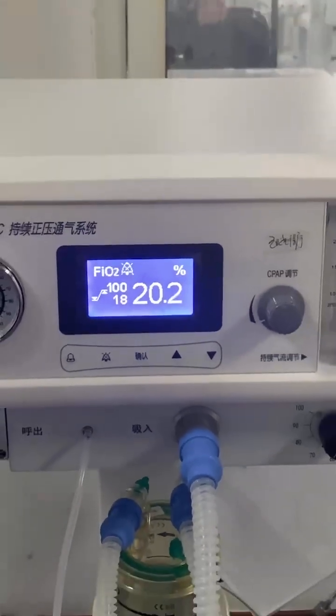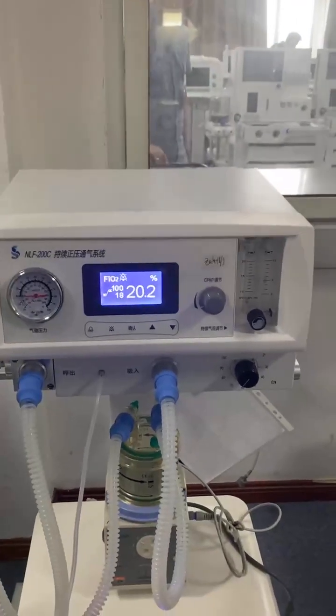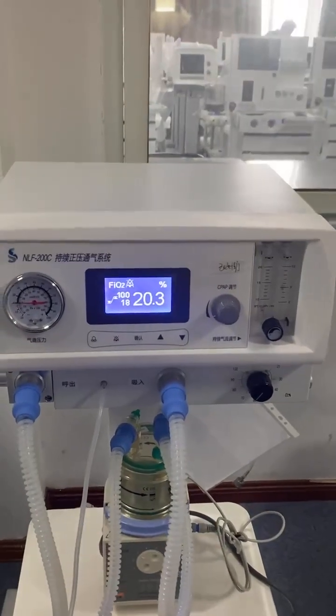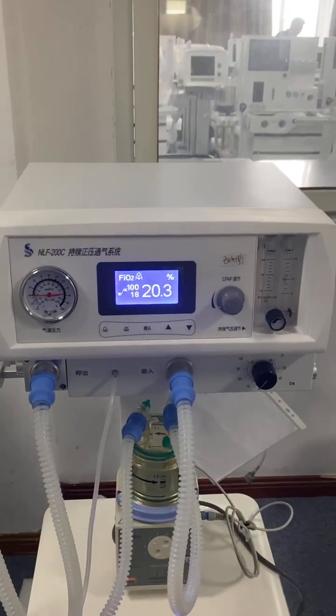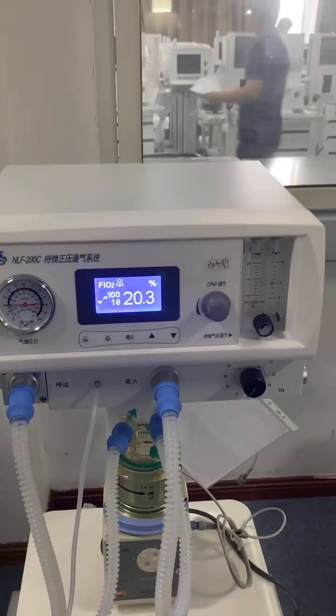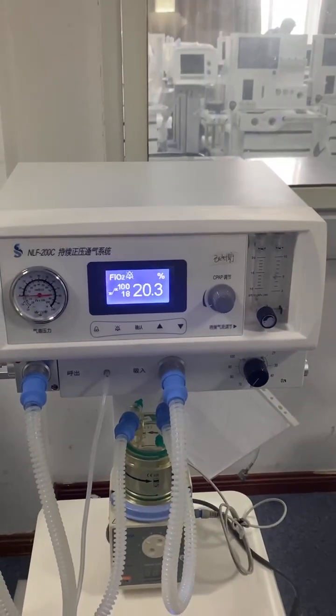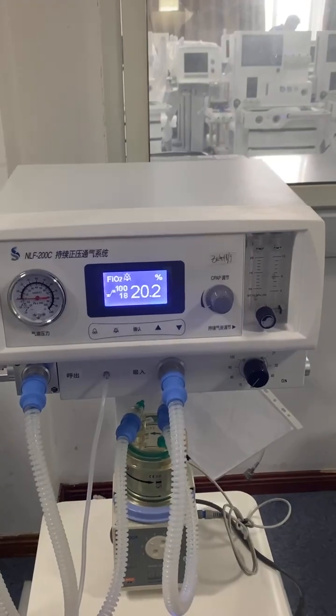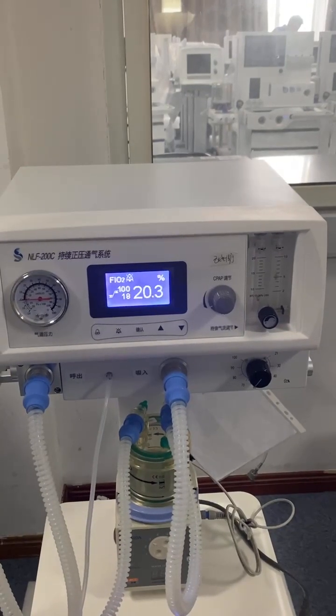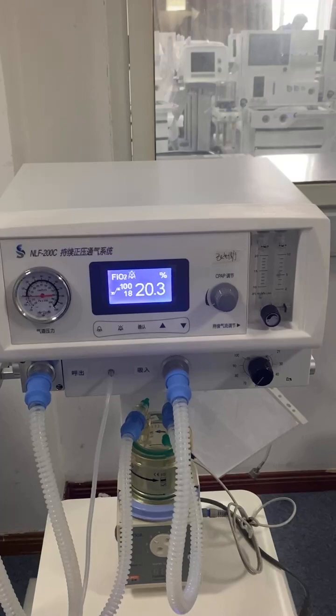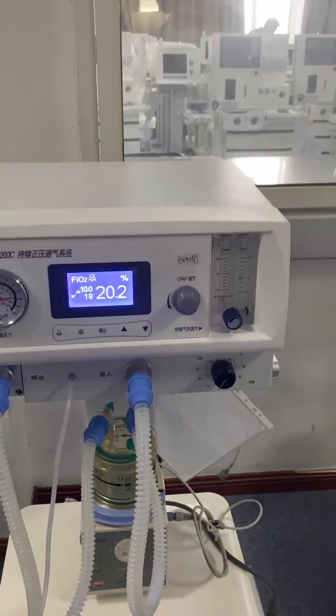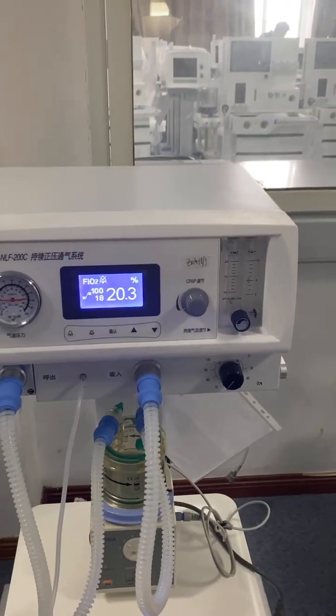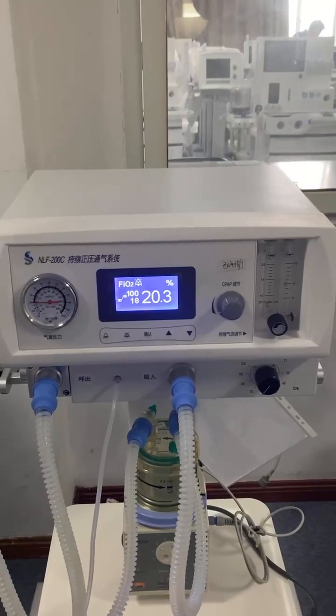Then I will also let you know how to adjust the oxygen concentration, because in different countries the oxygen concentration in the atmosphere is different. For example, in China we get 20.3 or 20.4, but maybe in your country it's around 21.2 or 21.3. So if we want all of the parameter settings and monitoring to be very accurate, we must do this 1 time after the installation. Then the machine can be used very accurately.